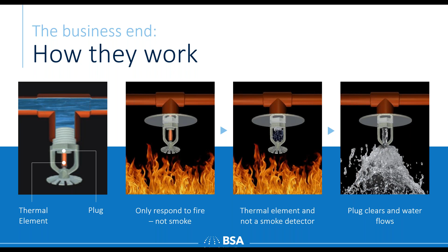And what you see in the movies where somebody presses one button and they all go off at once is complete rubbish. You'd need to individually go along and break all the different heads, like the thermal elements and all the heads to make them work for the basic sprinkler system. And the color of the liquid in the thermal element gives you an idea as to what temperature that sprinkler head goes off. In this example, the red liquid tells me this sprinkler head will respond to a temperature of 68 degrees C. So the temperature at that bulb has to get to 68 degrees C before it will break and the sprinkler will operate. And then any subsequent heads operating would also need to reach the same temperature.